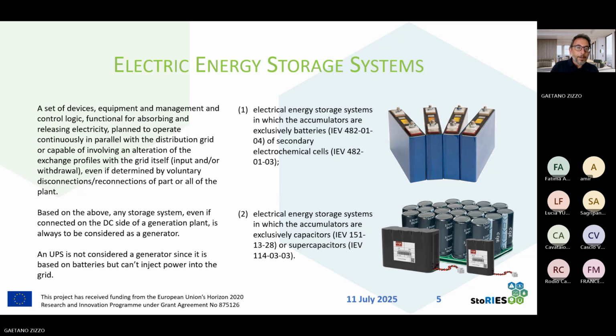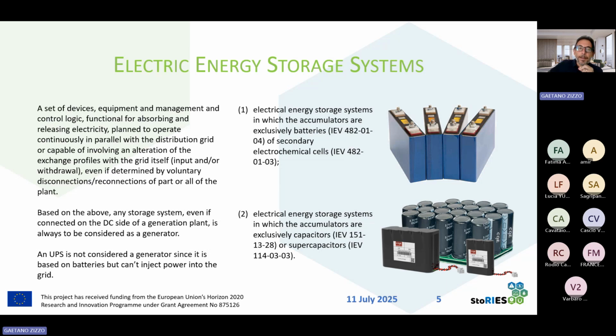Based on this definition, an uninterruptible power supply is not considered a generator, since it is based on batteries that can only take energy from the grid and inject the power towards the load. All other solutions comprising bidirectional converters that are not considered UPS are instead considered generators. And this definition comprises two kinds of electric energy storage system: electrical energy storage systems in which the accumulators are exclusively batteries or secondary electrochemical cells, and electrical energy storage systems in which the accumulators are exclusively capacitors or supercapacitors.